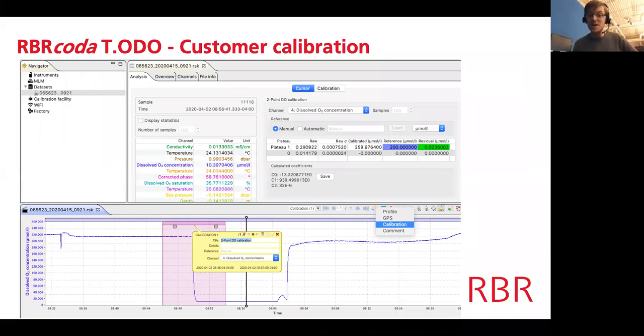So we have also implemented a customer calibration routine in Ruskin to do a linear offset and slope correction on top of the calibration polynomial to correct for any drift to the sensor. To perform this calibration, the sensor is placed into a 0 solution, which is prepared using sodium sulfite, and a 100% solution, which is prepared by simply bubbling air into a bath of water. And the calibration routine is performed on the RSK file, where you use this annotation feature. So when you select this button, you can choose the calibration, and then you highlight the region of your data set that shows those 2 different points. You can have Ruskin identify plateaus automatically, or you can select them manually. Once the plateaus are set, you can enter your reference values, and new coefficients will be generated in the analysis tab up here.